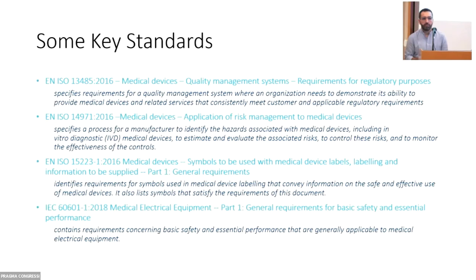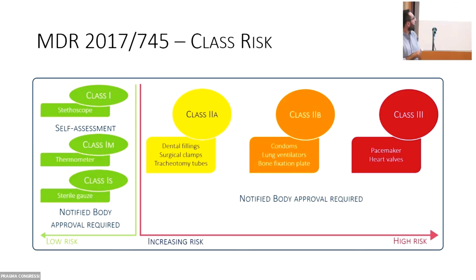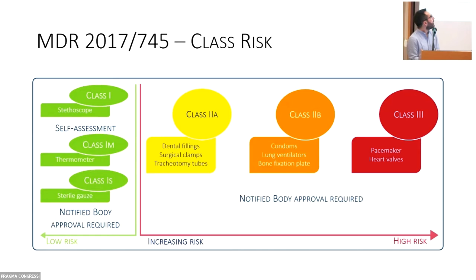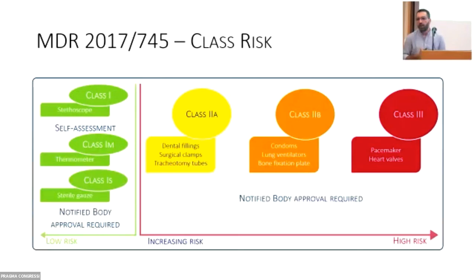Regarding the risk class, coming one slide back, according to the risk class, you need to have an approval from a notified body for classes that include high-risk devices. Instead, for classes with low-risk devices, you can go for self-assessment, but it's important that you keep all the documentation. But for some specific devices that are called class 1 for measurement, such as thermometers, or class 1 including sterile elements, you need the approval from notified bodies anyway, which is not coming to check each device, but only some features of your production line. In this case, it's going to check if your sterilization system is working, or if the physical principle of your device is correct or not, and the way you calibrate your device.